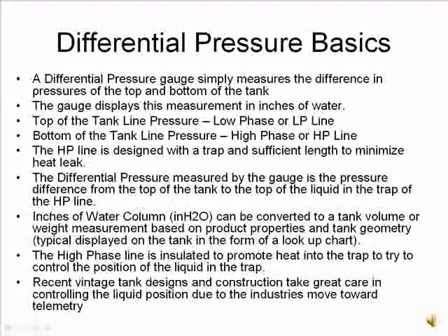The gauge displays this measurement in inches of water. The top of the tank's pressure is communicated to the outside of the tank using a small stainless steel line. It is called a low phase or LP line. The bottom of the tank's pressure is communicated using another stainless steel line called a high phase or HP line. The HP line is designed with a trap in sufficient length to minimize heat leak.